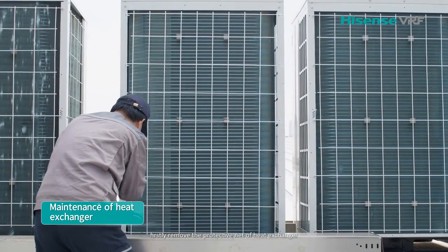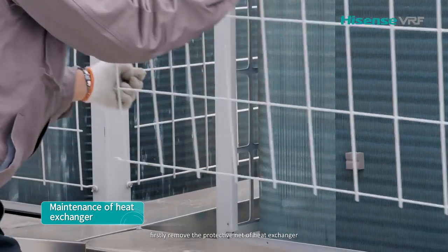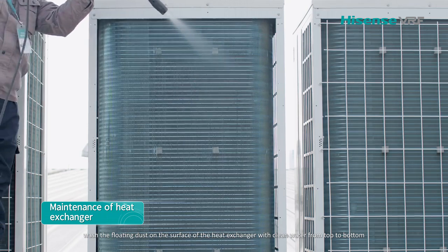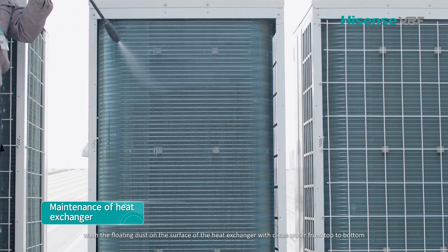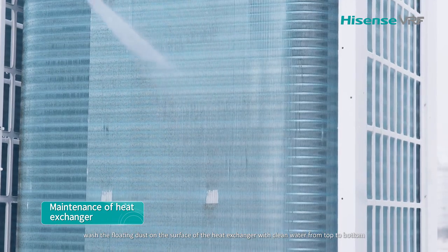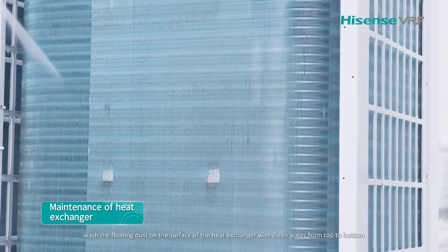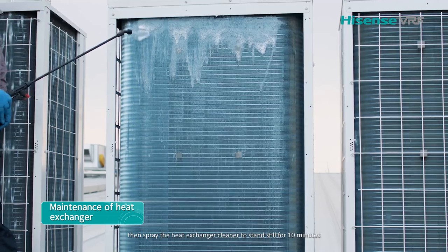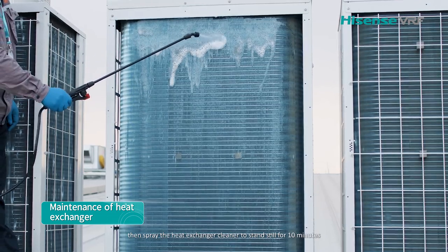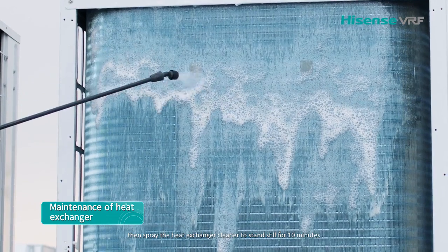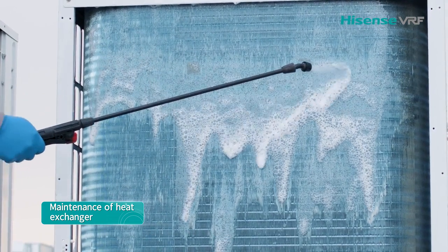Firstly, remove the protective net of heat exchanger. Wash the floating dust on the surface of the heat exchanger with clean water from top to bottom. Then, spray the heat exchanger cleaner to stand still for 10 minutes.